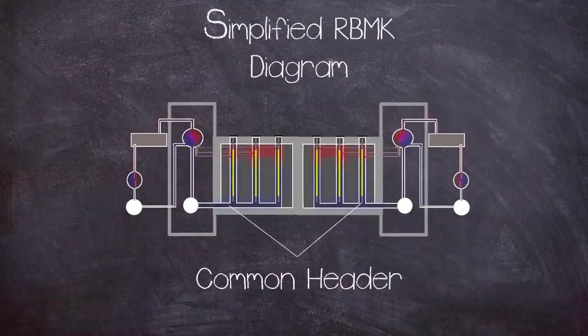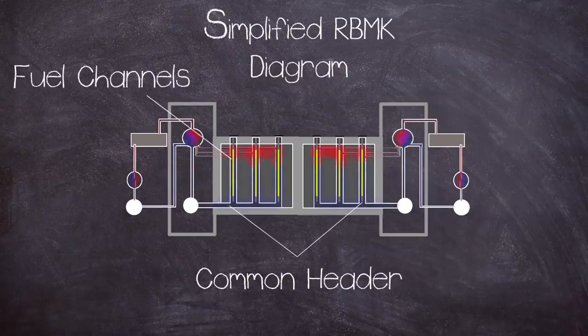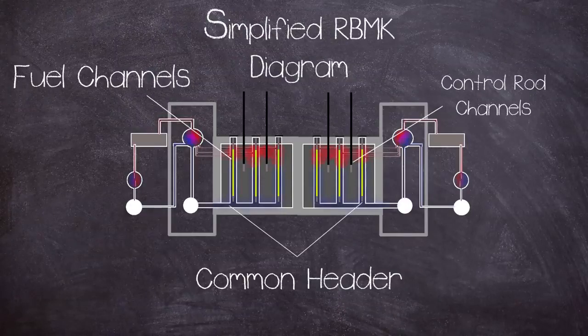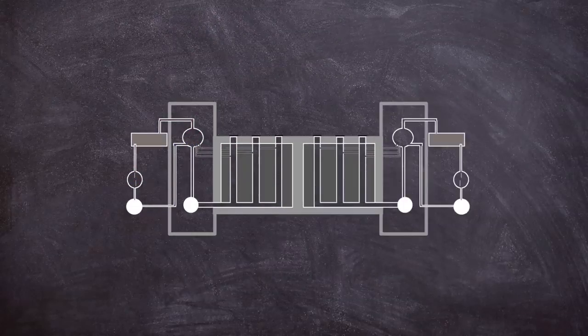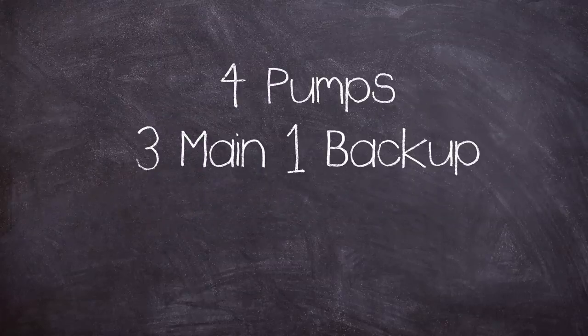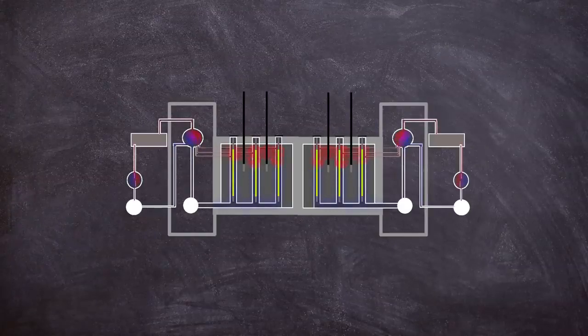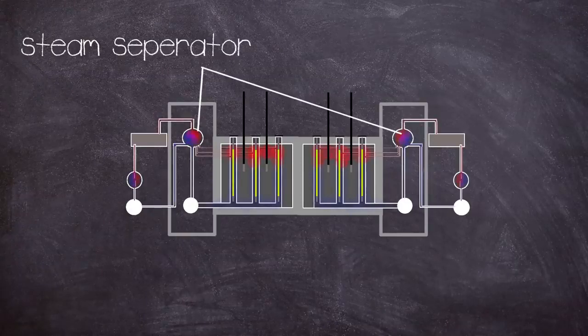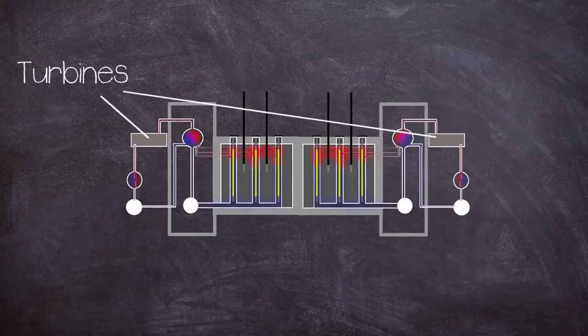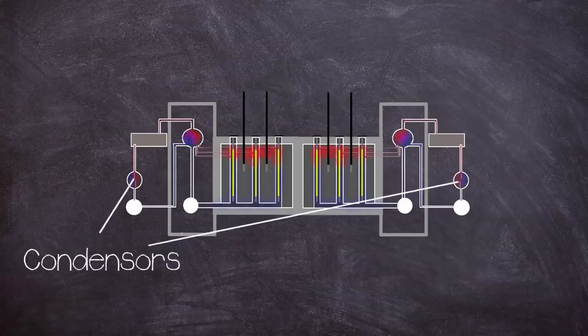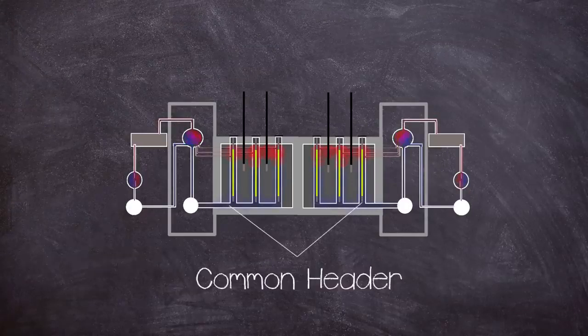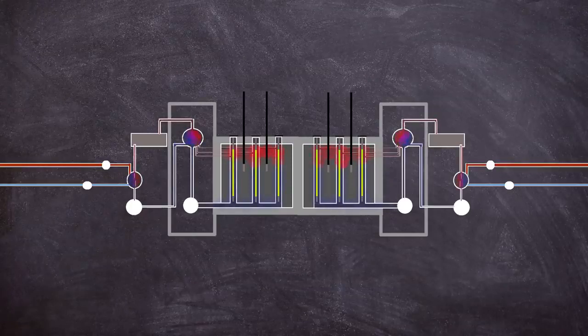The coolant was pumped through the core from the bottom common header through high pressure tubes that jacketed the fuel elements where the water would boil. Cooling water also circulated in control rod channels. Primary cooling was via two separate cooling circuits, one for each half of the core, meaning everything was doubled up with four main circulating pumps. As coolant boils, it exits the top and passes through a water-steam separator which takes steam to high then low pressure turbines generating electricity. Steam then passes through a condenser turning it back to water to be pumped back into the core. The condenser is cooled using a separate secondary water cooling circuit.